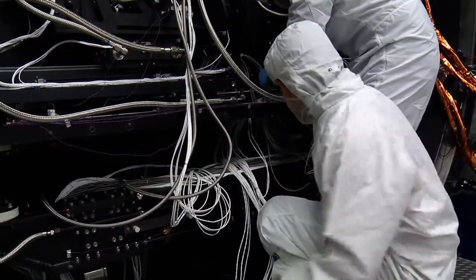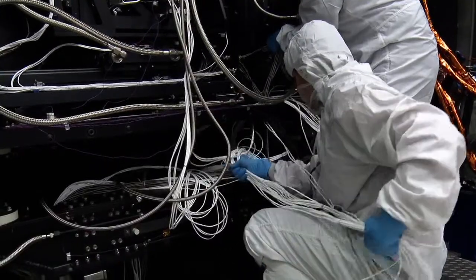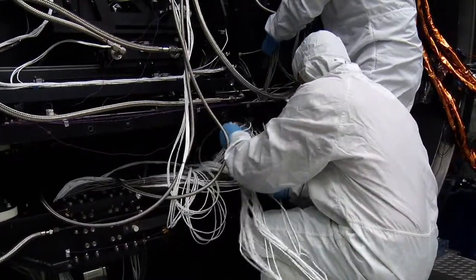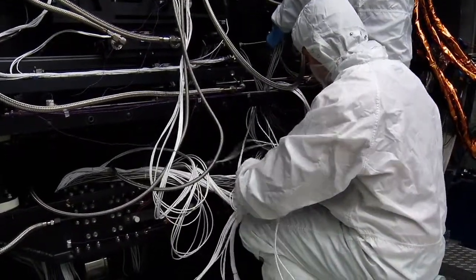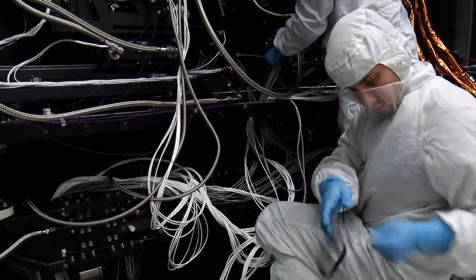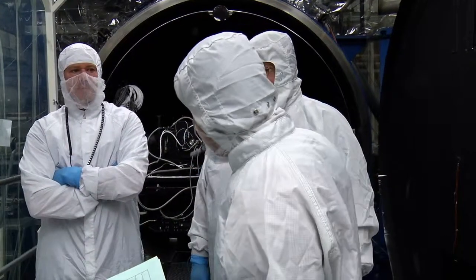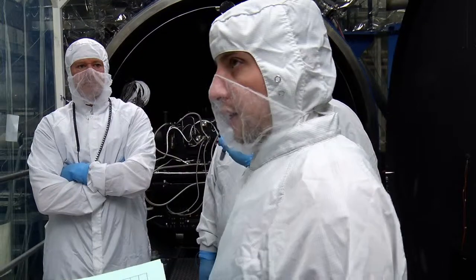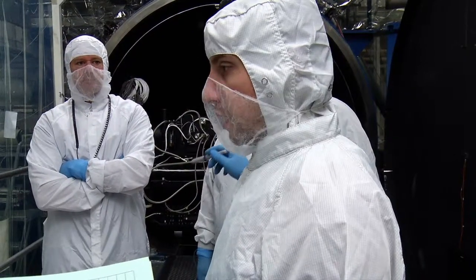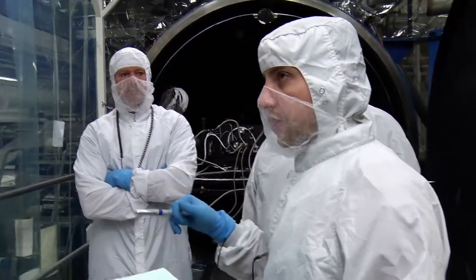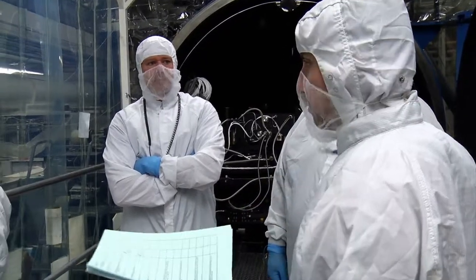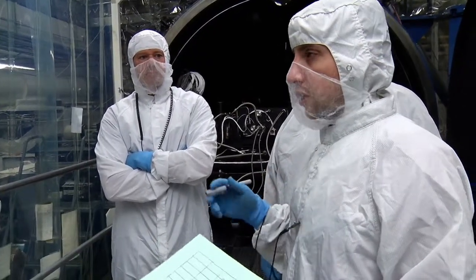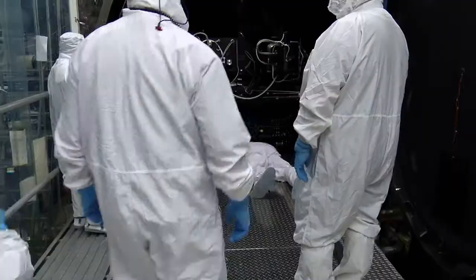Once satisfied with our inspection, we disconnect the wires and cooling lines from the instrument and the calibration equipment. Then we pull out the sled. And then we'll have 3 people out here pulling, and everybody else that's not doing anything is going to be monitoring, making sure we don't catch any harnesses, cables, or whatnot.